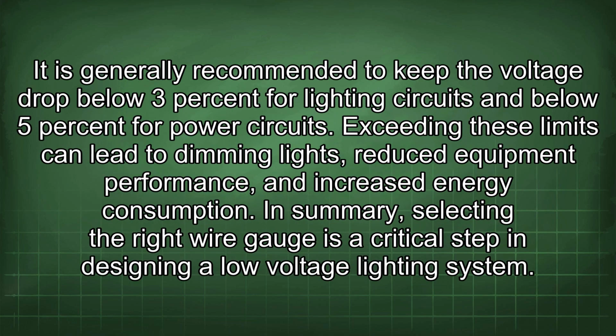It is generally recommended to keep the voltage drop below 3% for lighting circuits and below 5% for power circuits. Exceeding these limits can lead to dimming lights, reduced equipment performance, and increased energy consumption.